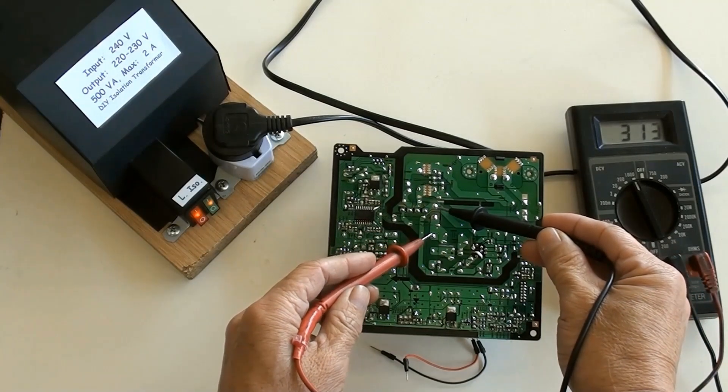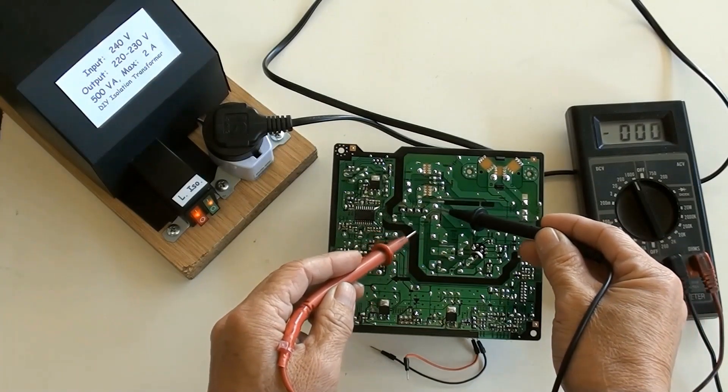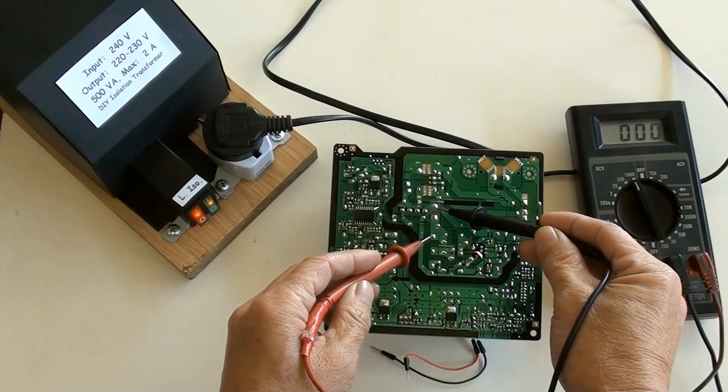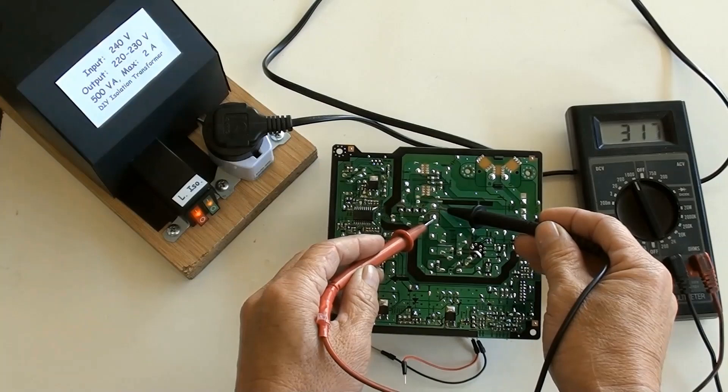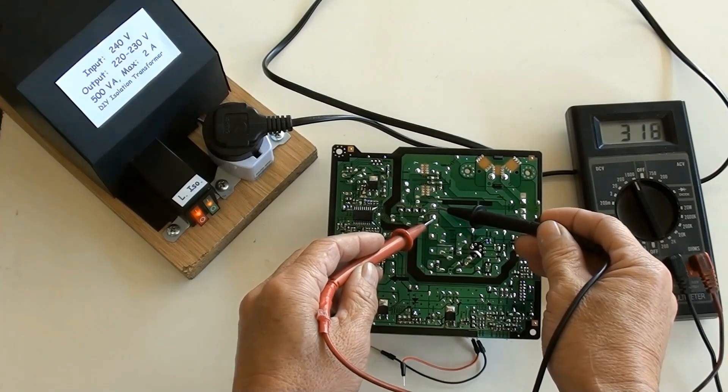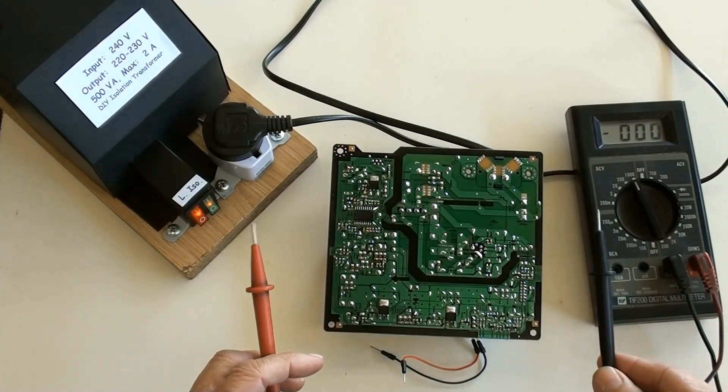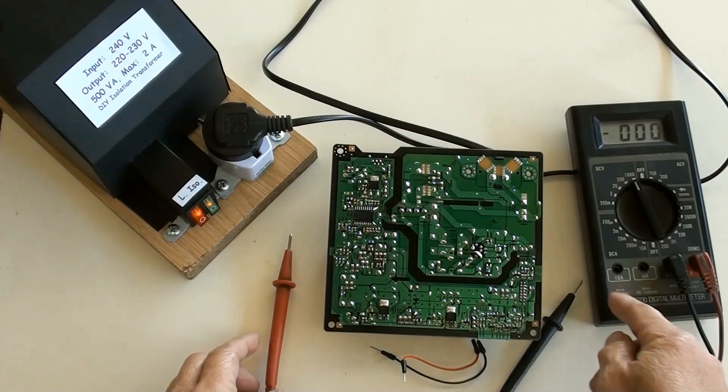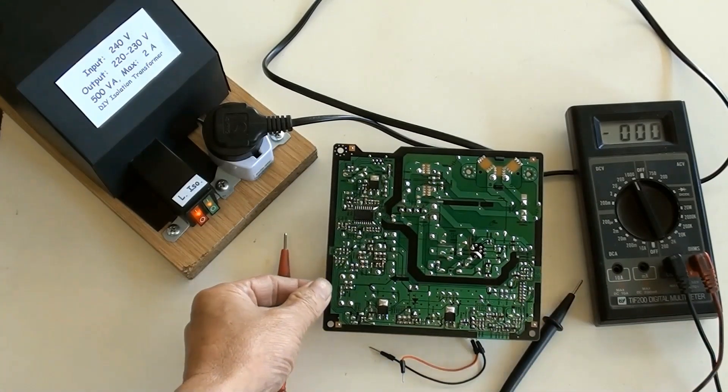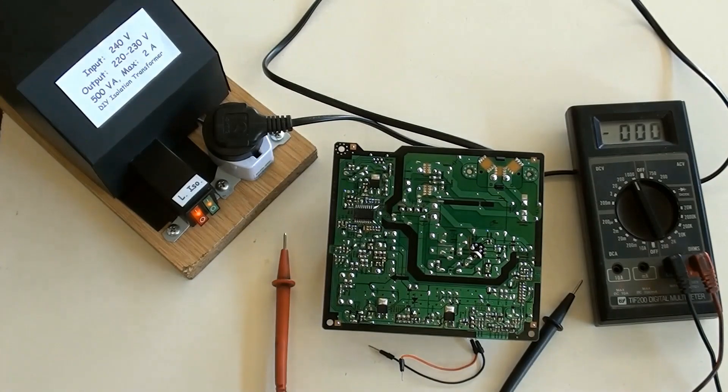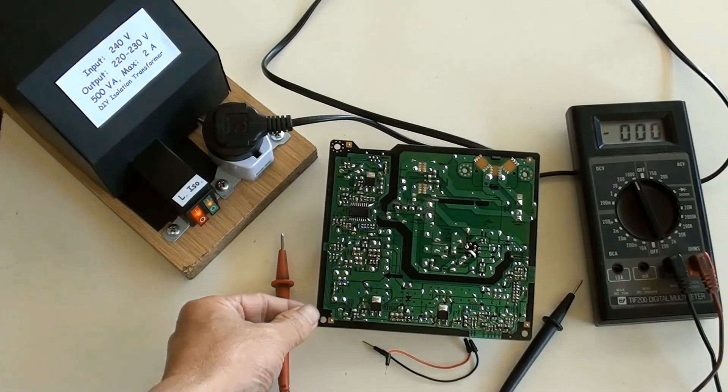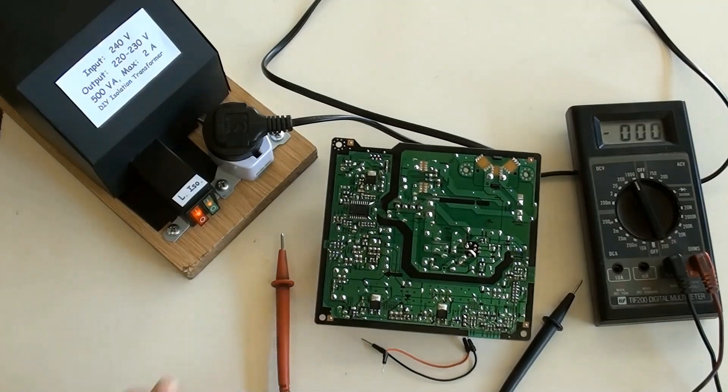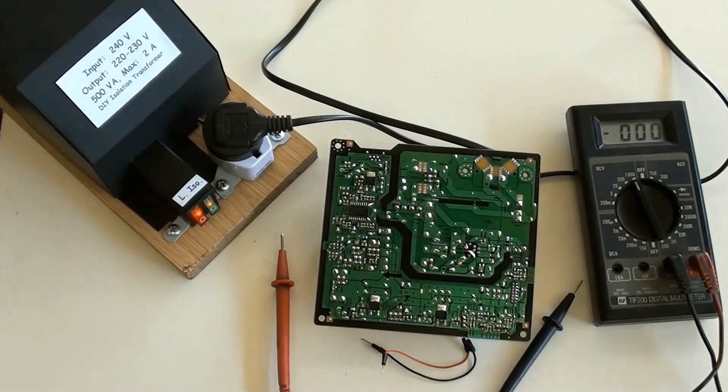During measurement or diagnostics by using a multimeter, your fingers might unintentionally contact the circuit board on the high voltage part. As long as you touch one part only, like this, you would not get electric shock. That is the advantage of using an isolation transformer in this circumstance.